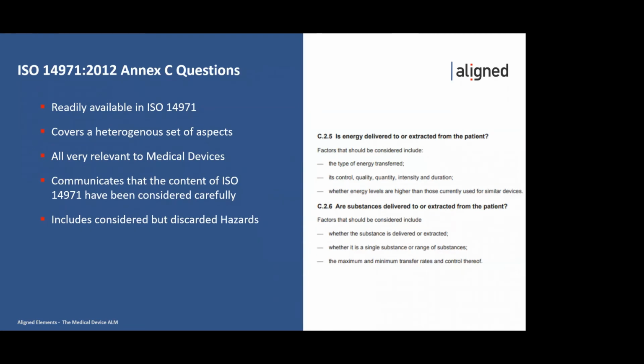But the relevant thing here is that it does consider things that are very relevant to medical devices, like energy, like substances, like user involvement, etc. So it's very tailored for identifying risks in medical devices. And again, just like the hazard category list, I think it's great to go through these kinds of questions and see if there are any risks that can be identified from them.